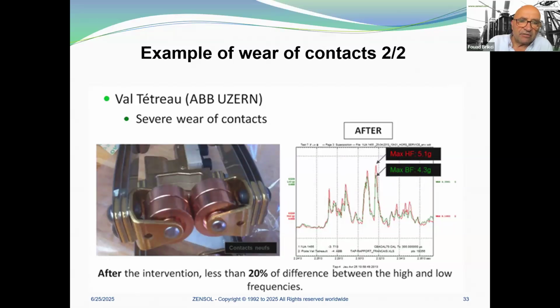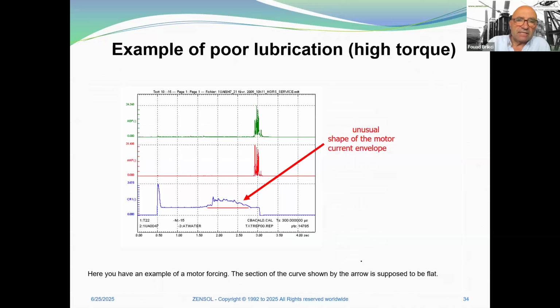So after the intervention, there is less than 20% difference between the high and low frequencies. So the high and low frequency is a good tool. It works in 80% of the cases to detect contact wear, and sometimes it does not work. Here it's a very quick problem that you can find with only the motor current.